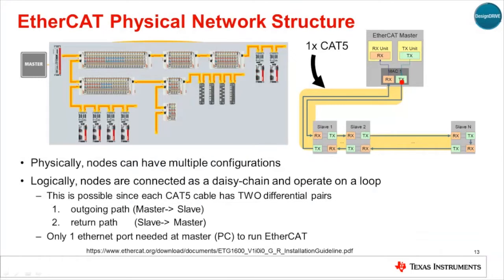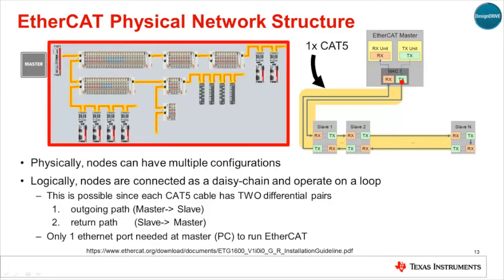EtherCAT is an Ethernet-based Fieldbus standard targeted at real-time requirements for automation. It is designed to achieve very low update or cycle times, typically less than 100 microseconds, with low jitter less than 1 microsecond. Physically, the nodes of an EtherCAT network can be connected in a number of configurations, as illustrated in the diagram at the upper left.